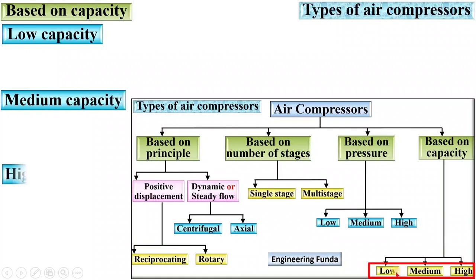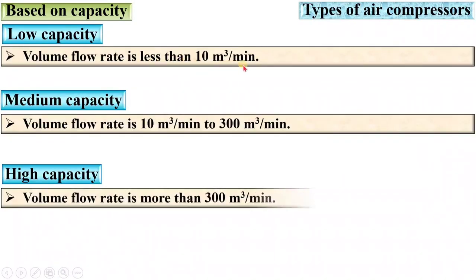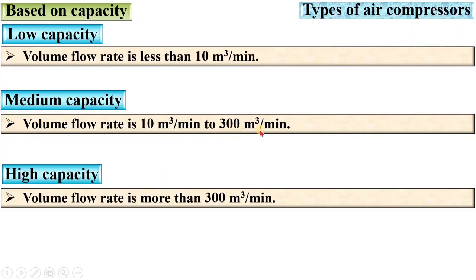Based on capacity: low capacity compressor has a volume flow rate of less than 10 m³/min; medium capacity is 10 m³/min to 300 m³/min; and high capacity has a volume flow rate of more than 300 m³/min. Remember these two figures: 10 and 300.